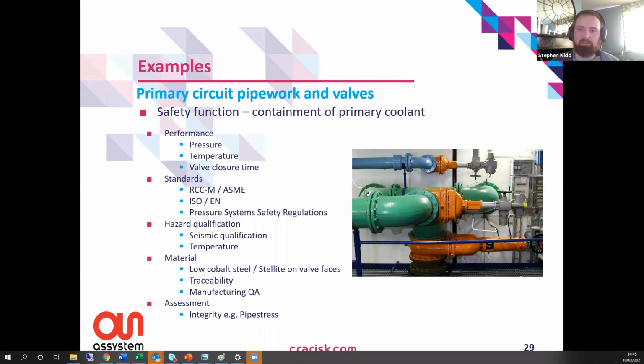And there may be some more unusual things like material issues. So if it's primary circuit pipework, we're worried about activation of steels, so they need to be low cobalt. We need to avoid things like stellite on valve faces, which is used because it's hard wearing. And material traceability in manufacturing QA. As I said before, if we're making very high integrity claims, then we really need to clearly understand where the materials come from, how they've been manufactured, and at each stage of the process have evidence to show that it has got the correct makeup and will have the right strength and everything at the end. And then there may be specific assessments, like pipe stress, for instance, which is used to demonstrate the integrity of pipework.